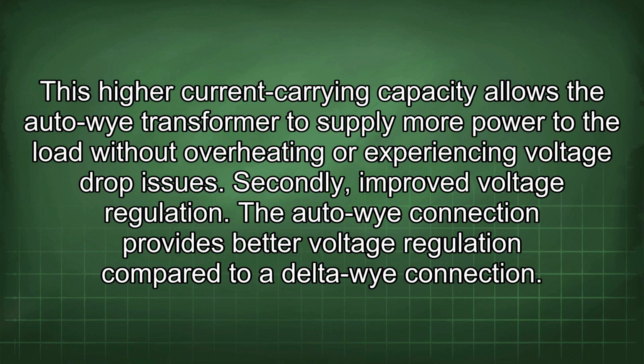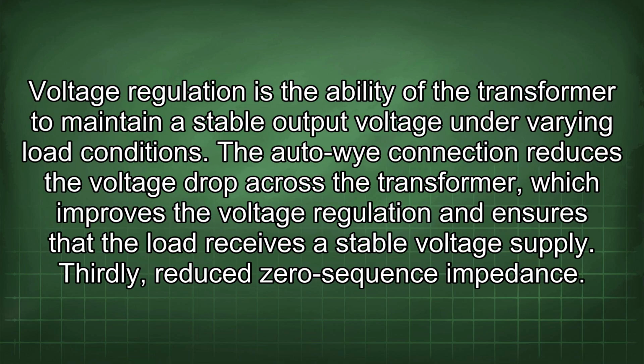Secondly, improved voltage regulation. The Auto-Wye connection provides better voltage regulation compared to a Delta-Wye connection. Voltage regulation is the ability of the transformer to maintain a stable output voltage under varying load conditions. The Auto-Wye connection reduces the voltage drop across the transformer, which improves the voltage regulation and ensures that the load receives a stable voltage supply.